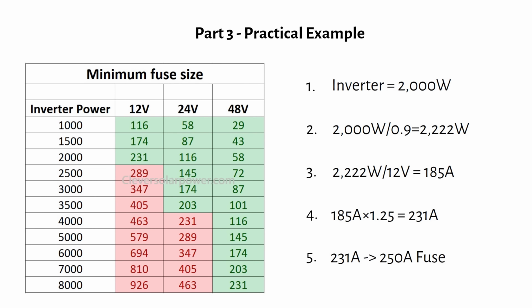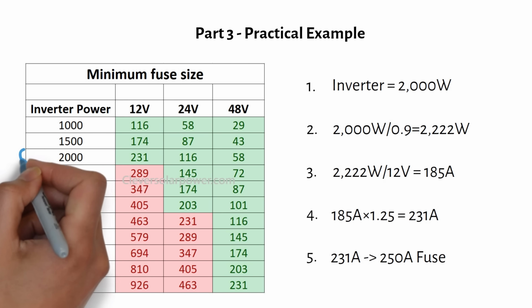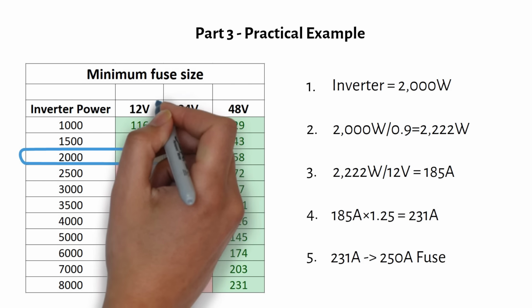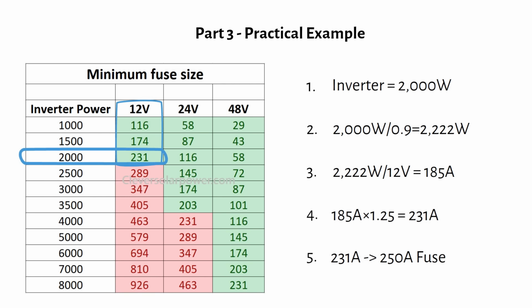To make it easy for you, I have created a table with different inverter power ratings at different voltages, so you can easily see which fuse you need without doing all the calculations yourself. You will have to round up to the nearest fuse size. As you can see from our example, we used a 2000 watt inverter at 12 volts. So we need at least a 231 amp fuse. So we choose the next fuse size at 250 amps. The size of the available fuse depends on what kind of fuse you choose, and I will talk about it next.